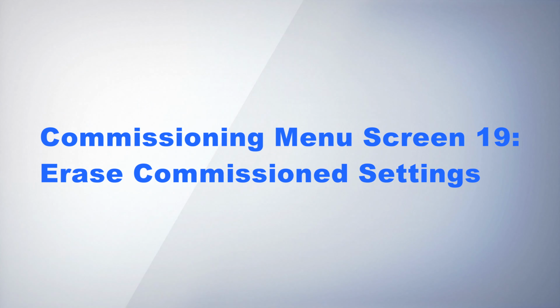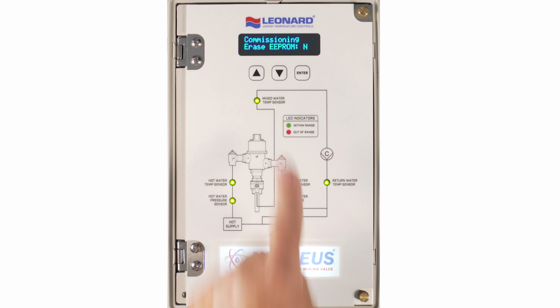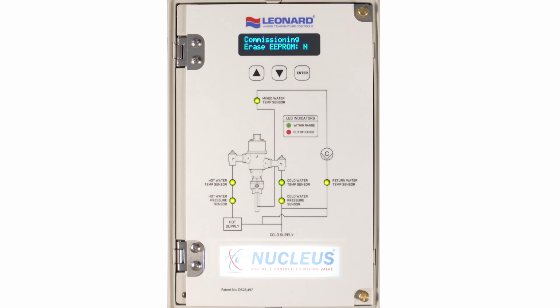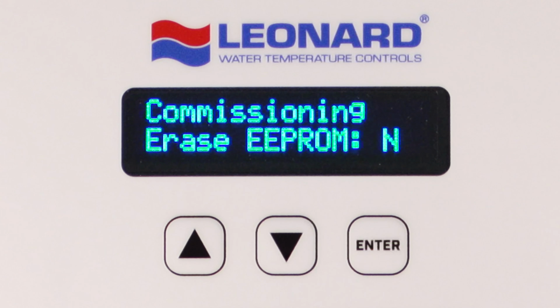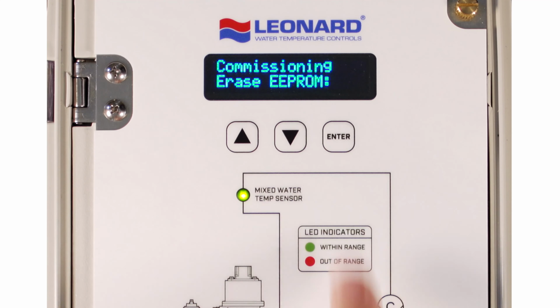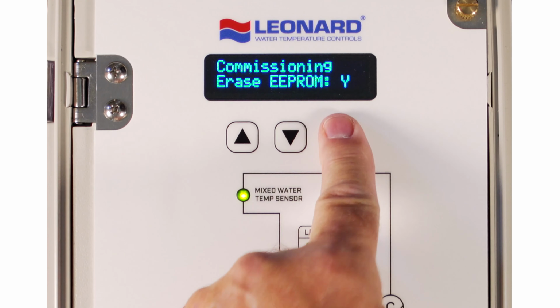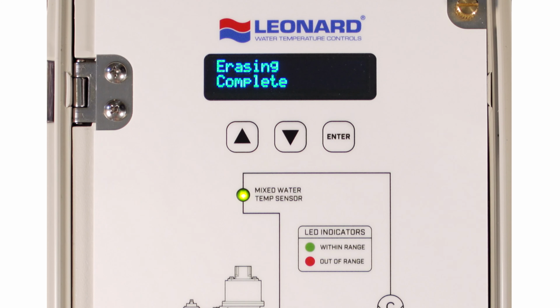Commissioning menu screen 19. Erase commissioned settings. Pressing down 18 times displays Commissioning Erase EEPROM, No or Yes. This feature allows the user to erase the electrically erasable programmable read-only memory. Entering Y will decommission the controller and return it back to factory settings. Once decommissioned, the controller will no longer display or send errors to the building management system, and alarms will no longer be triggered. These features will be inactive until the controller is recommissioned.